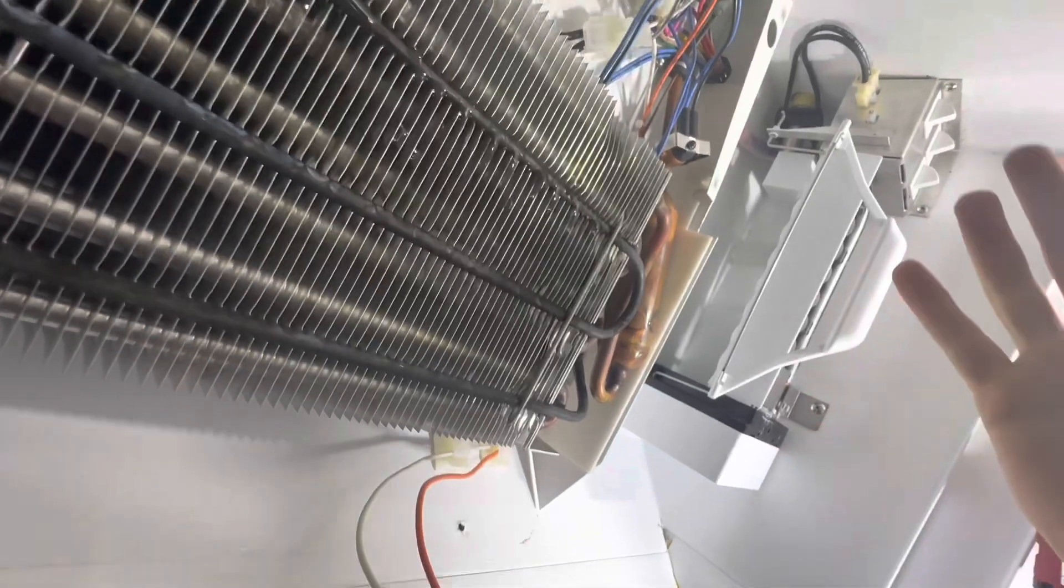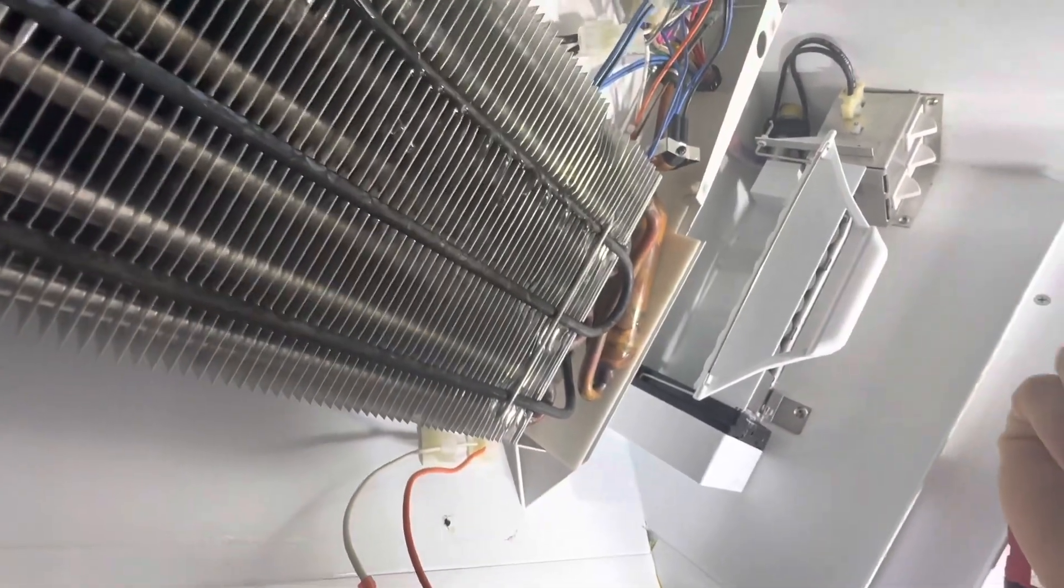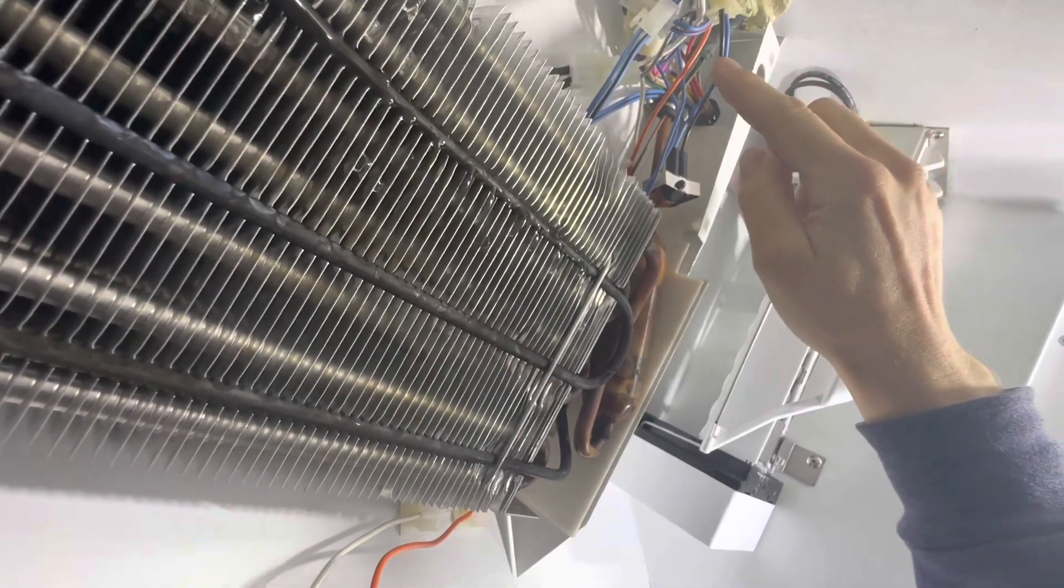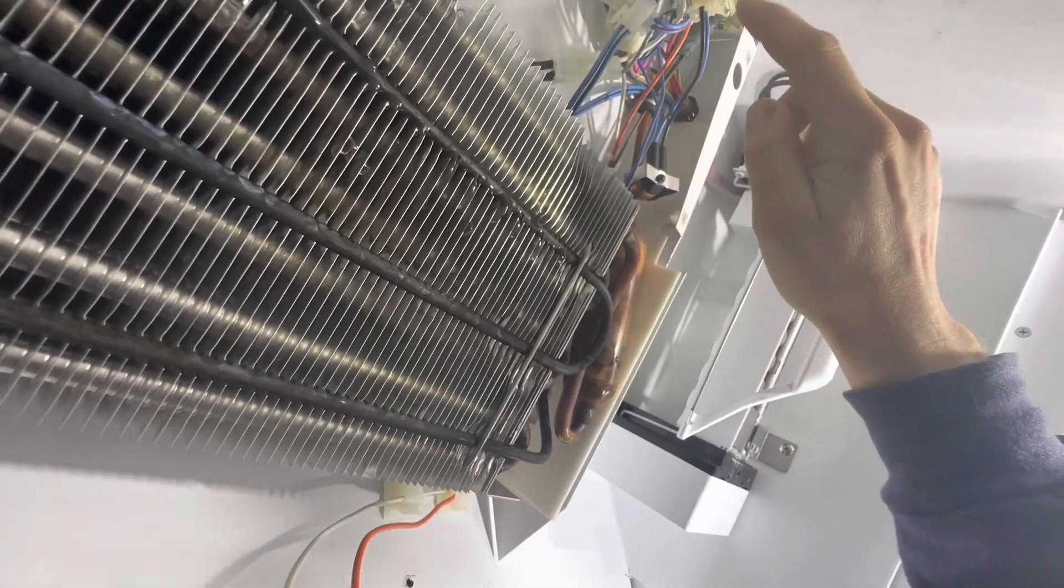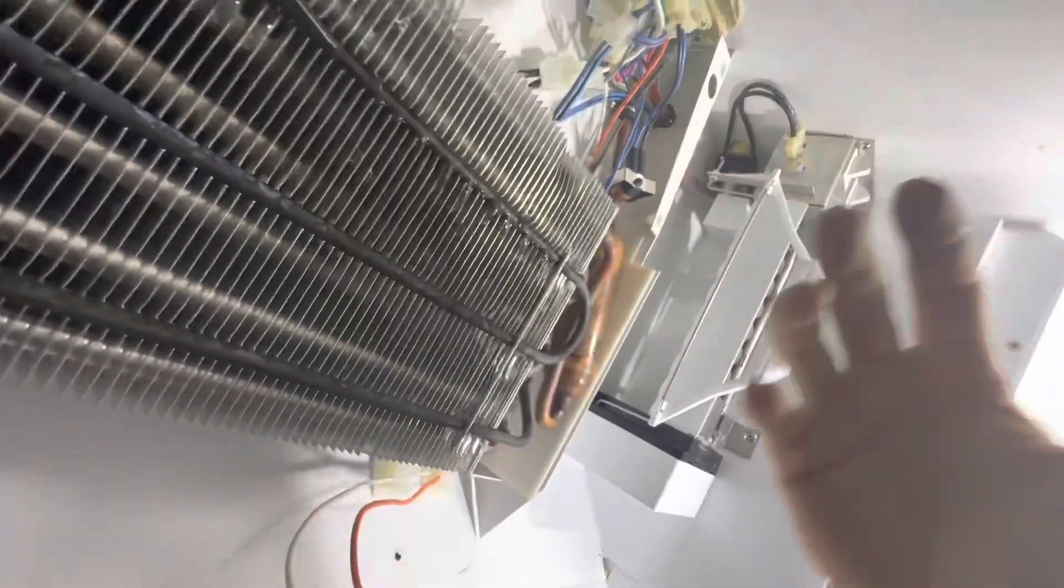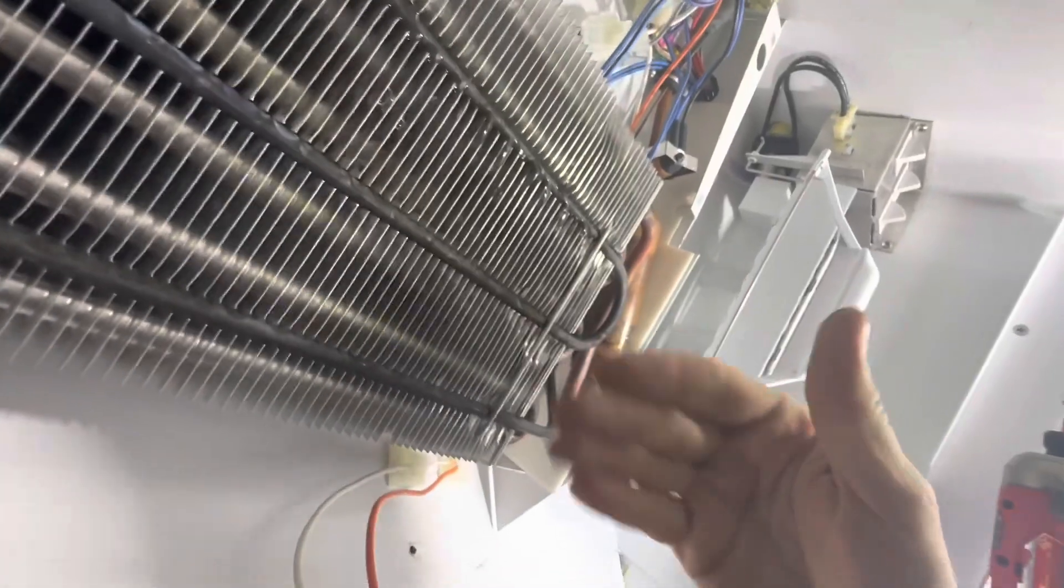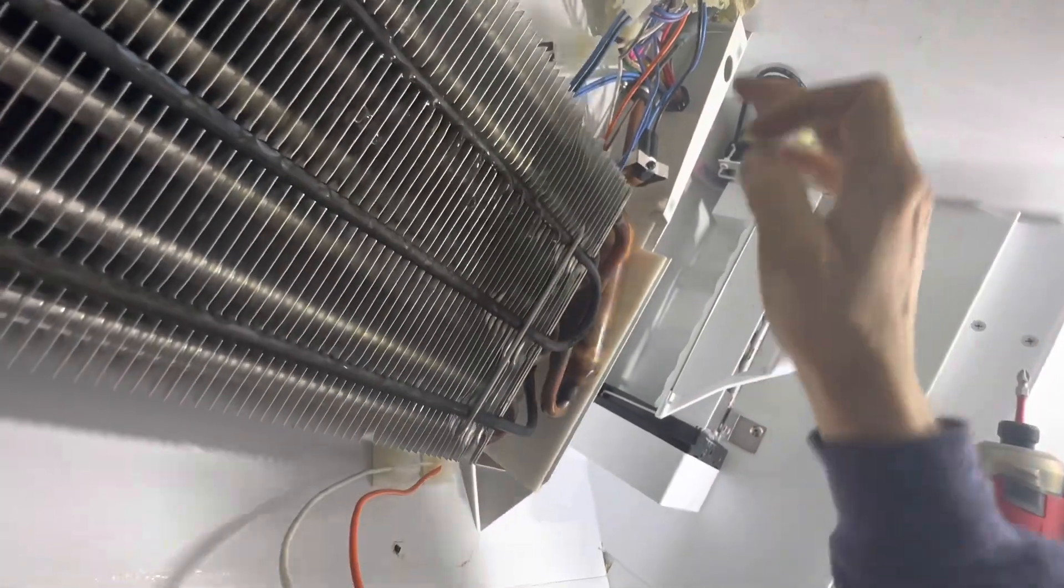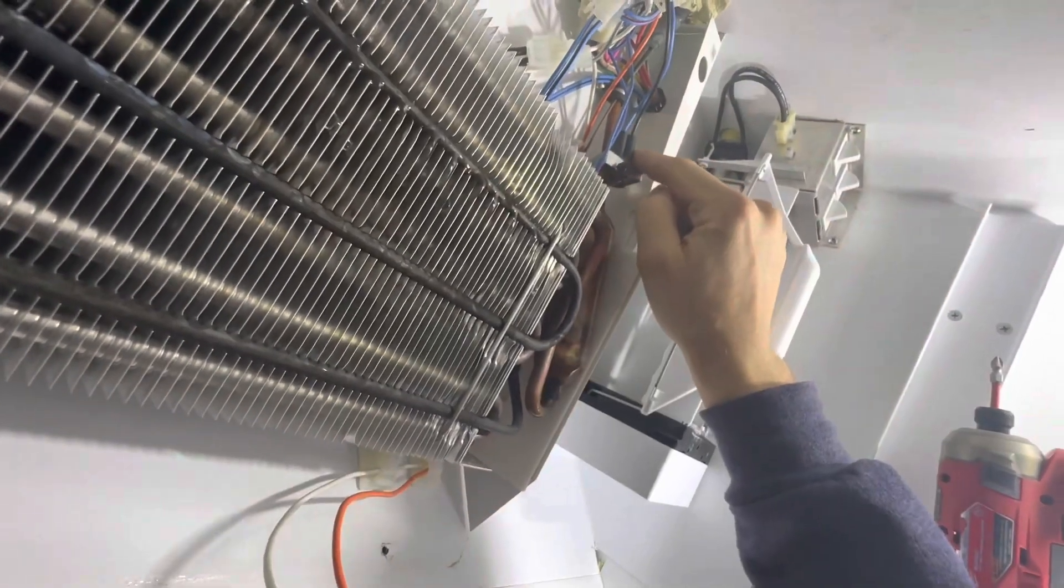The heaters are generally on a timer and they come on every couple hours. Let's go ahead, throw this into defrost, and see if we get power through our termination switch. If we don't get power through our terminator switch and this machine's at temperature zero degrees, our coil's been defrosted, it's been running for about an hour, it should be perfect. We should be getting power to our heaters. If we don't, I would go ahead and say that we have a bad terminator switch. Let's test it out.